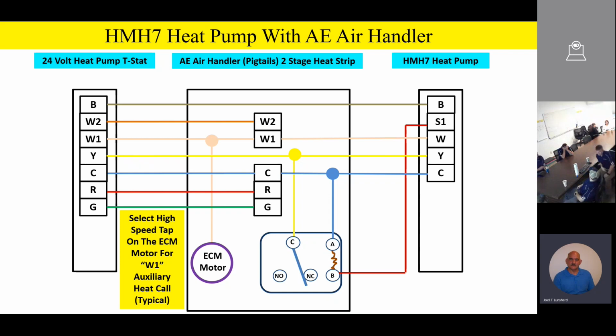Now on the ECM motor, we're also going to select a high-speed tap on the motor, so that anytime we have an auxiliary heat call, we're going to drive that motor to high speed. Now this is very, very typical. You can still adjust this if you want to, but a good place to start is to just go on the high-speed tap. The idea being is this: anytime we have an auxiliary heat call, we're going to drive that fan to high speed. That way we don't overheat the heat strip and so on. So that's very, very typical that we'll see that.